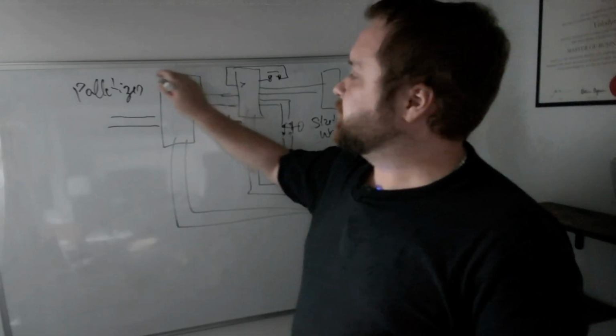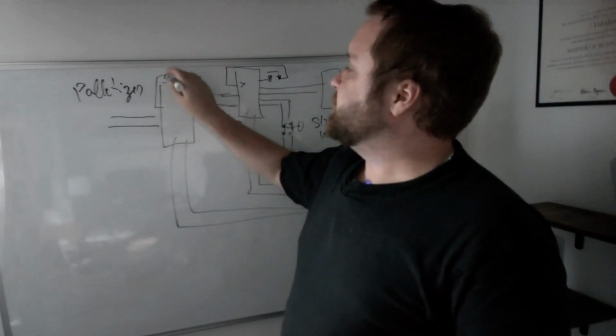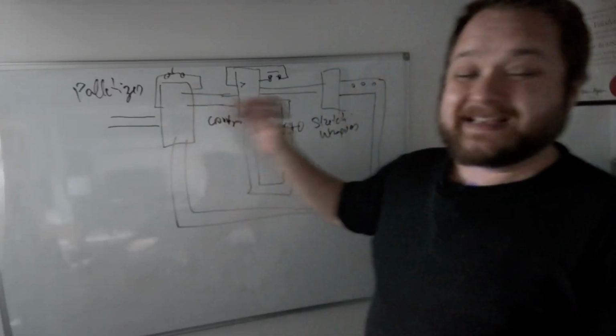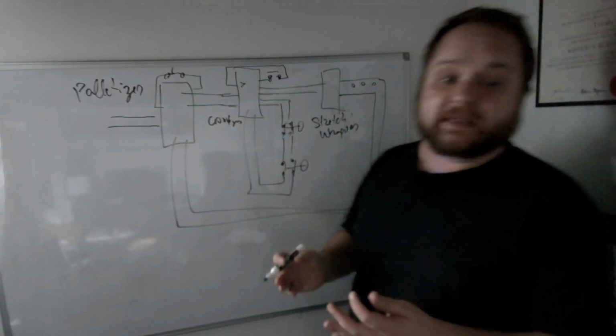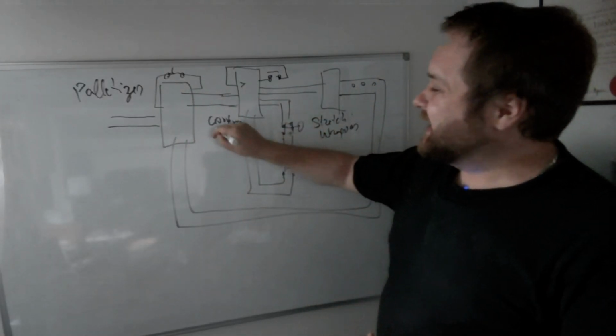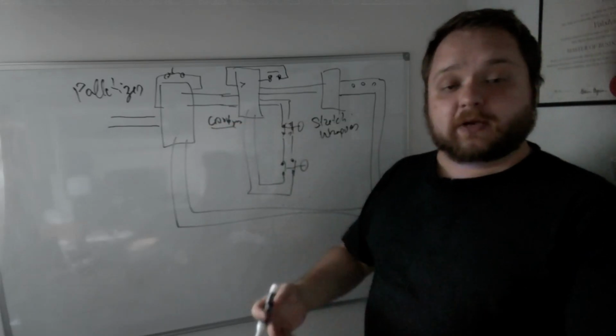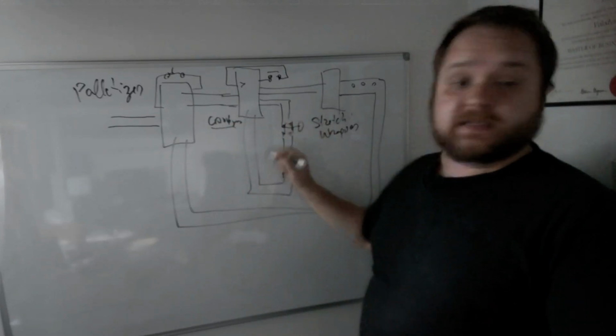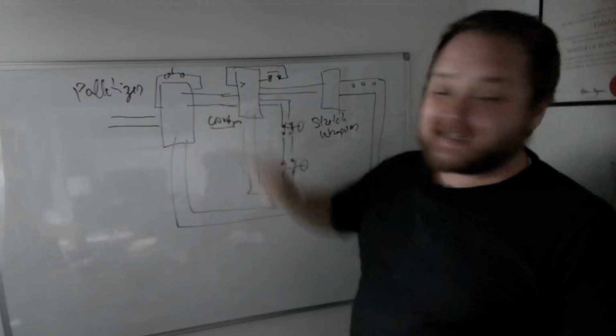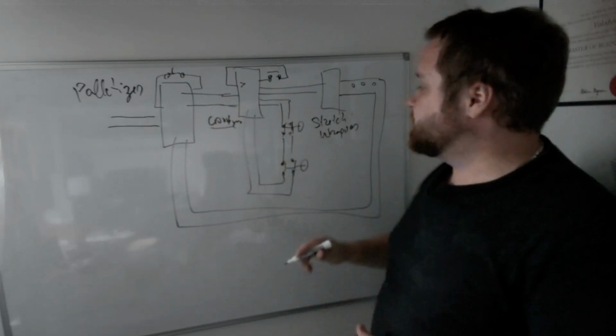And basically this is going to have its own push button for reset. Again, this is not overly complicated yet. We'll talk about even more complicated scenarios, but you have a conveyor system that is allowed to run, again, based on its own e-stops, while the palletizer may not be satisfied on the safety side.